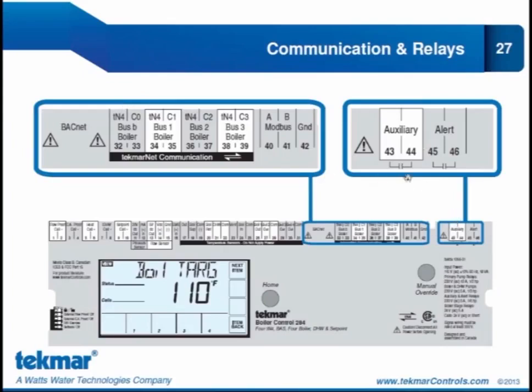Over here we have our auxiliary and our alert relays. Our auxiliary relay, terminals 43 and 44, can be used to connect either a domestic hot water recirculation pump or the combustion air damper. It's one or the other. We only have the single relay. And we have the alert output as well. There is an exclamation point here because if you are connecting the domestic hot water recirculation pump, it will be line voltage. So it is the one area where we have line voltage on the upper side of the 284 control. The rest of the line voltage connections are at the bottom of the control, as we'll see next.